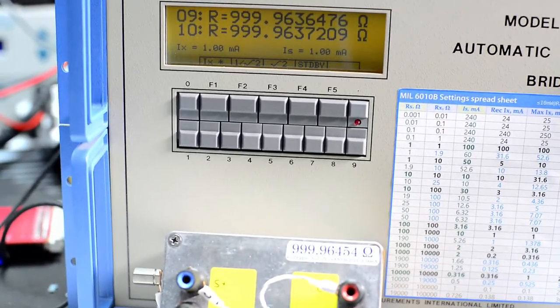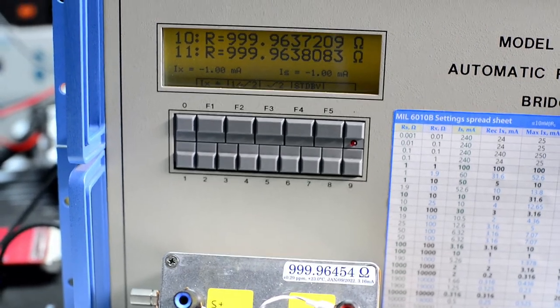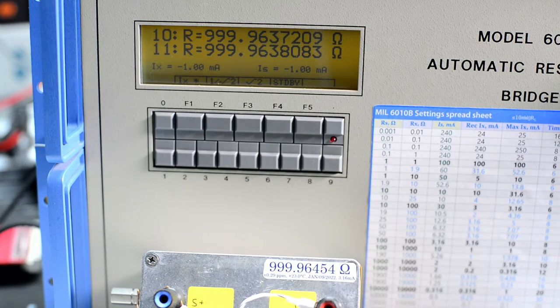So you can see it's almost there. Let's see what's there. I might actually run the calibration adjustment for the bridge using the outlined procedure in the documentation, and also I'll put the standards in the chambers so I can make sure the bridge is still giving good values, but that will not be very exciting for a live stream, and I think I'll do it offline.